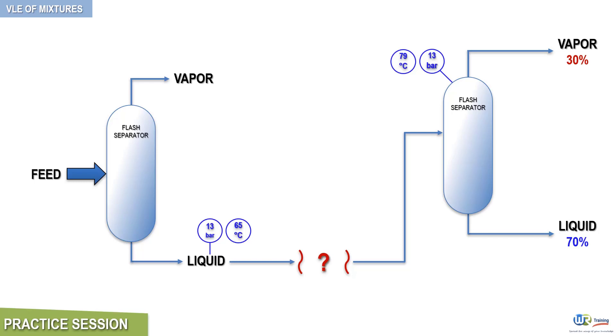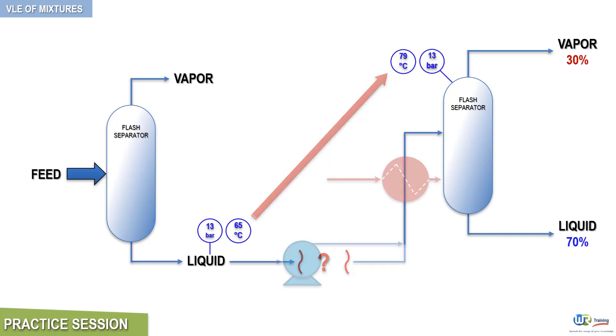The liquid mixture is available at the bottom of the first flash unit at 13 bars and 65 degrees Celsius. Therefore, we need to pass it through a heater in order to raise its temperature to 79 degrees Celsius, as that is the required operating temperature of the second flash unit. This operation involves a heat exchanger, but also a liquid mover type of equipment such as a centrifugal pump. A pump is needed to convey the liquid from the first flash unit to the heat exchanger, and then to the second flash unit, as depicted in this process arrangement.